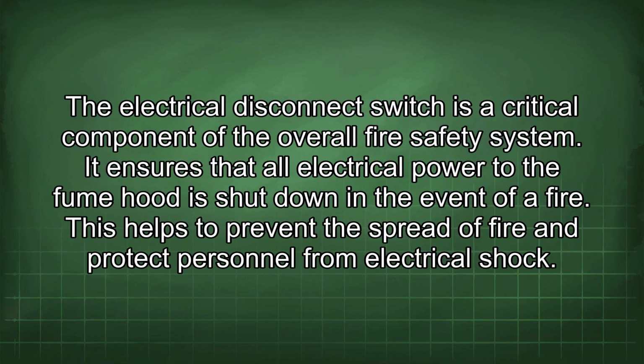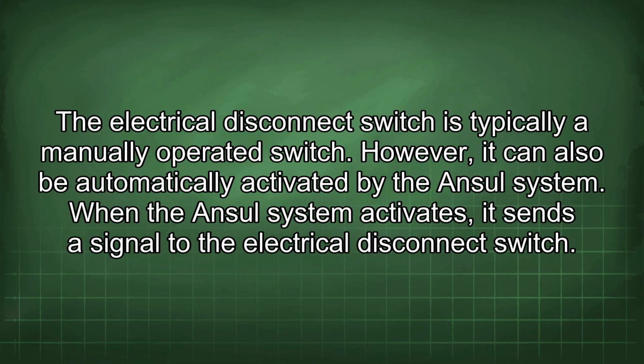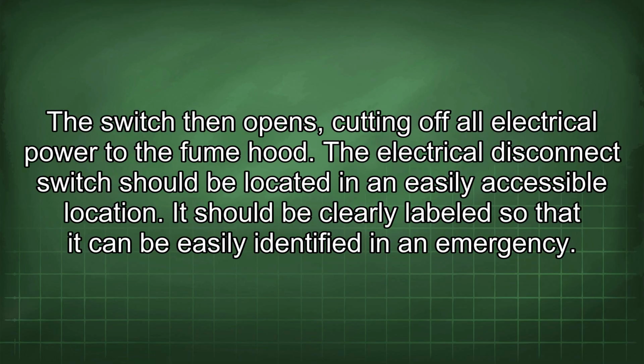The electrical disconnect switch is a critical component of the overall fire safety system. It ensures that all electrical power to the fume hood is shut down in the event of a fire. This helps to prevent the spread of fire and protect personnel from electrical shock. The electrical disconnect switch is typically a manually operated switch. However, it can also be automatically activated by the Ansul system. When the Ansul system activates, it sends a signal to the electrical disconnect switch. The switch then opens, cutting off all electrical power to the fume hood.